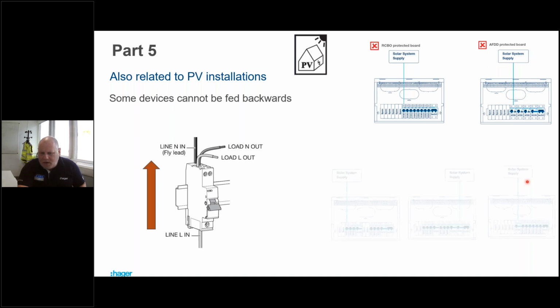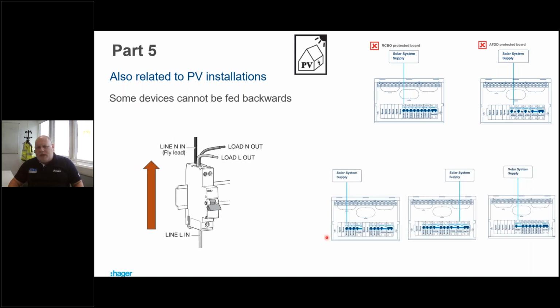But we can feed backwards through an MCB. MCBs are pretty much bulletproof. There's nothing really in there to get damaged apart from a bimetallic strip. So we can feed those backwards with current, not a problem. We do a double pole RCBO, which is double mod, we could feed that backwards, not a problem. So we've got some solutions there where we need to feed solar into a board, other than the main incoming device.